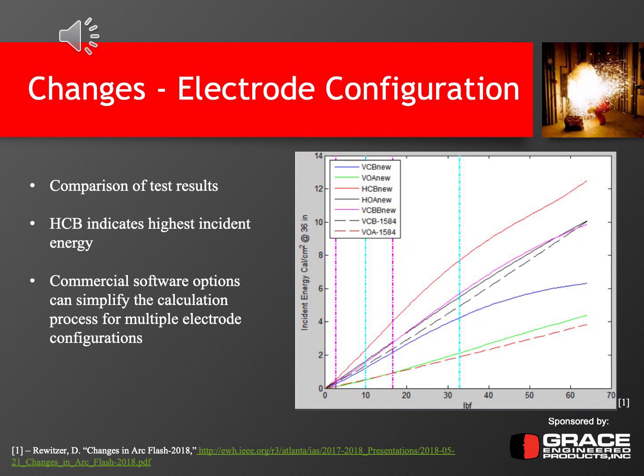The dotted lines in this were from the 2002 equations, or the test, while the non-dotted lines are from the new 2018. And if you look, the largest or most severe would be the HCB, the horizontal conductors in a box. That is the red line on the top, followed by VCBB and HOA, or horizontal open air. So those are your most severe. Then the dotted line is the VCB, and the new VCB is the blue line.